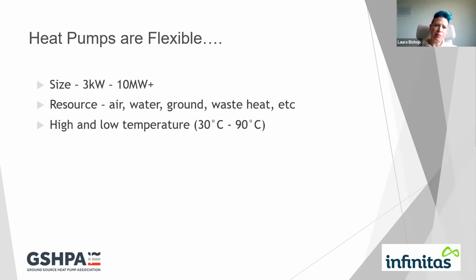And in terms of temperatures, most people I think would say, oh, the heat pump can only do 40 degrees C. Actually, depending on the refrigerant and the type of heat pump you're using, you could have anything from 30 degrees C up to 90, 95 degrees C if you're using something like ammonia. So it's about having the right heat pump for the right application. Of course, heat pumps can do heating and cooling. So if you're traditionally having a gas boiler to do your heating and a chiller to do your cooling, the same machine, you can have a heat pump that will do both, and you can either have it doing heating or cooling, or you can have it doing simultaneous. So it can be a saving on plant, because you can have one machine instead of having 2 separate machines.